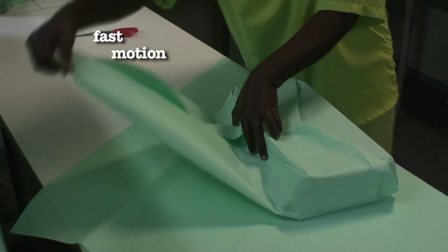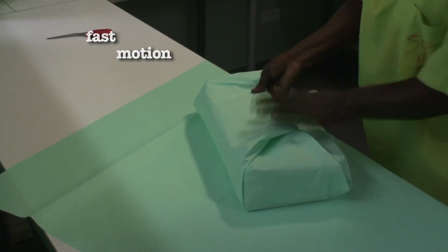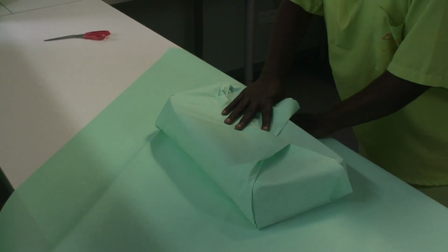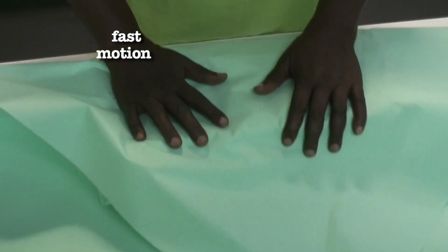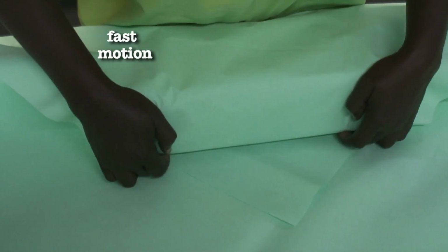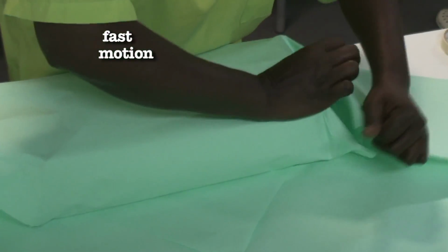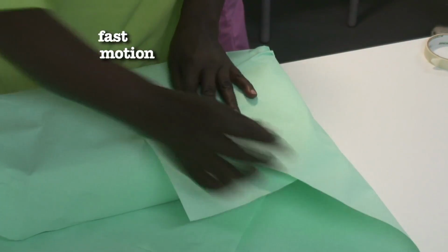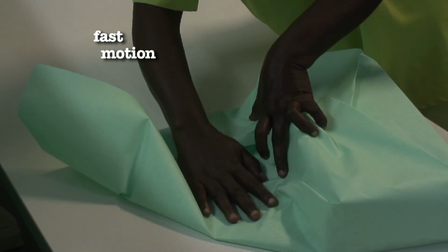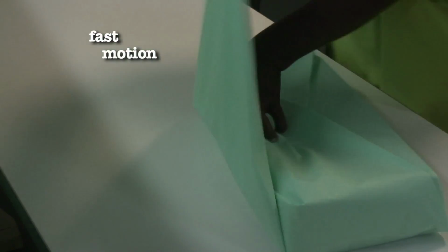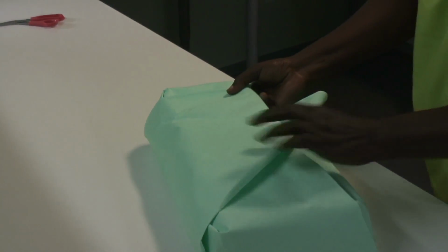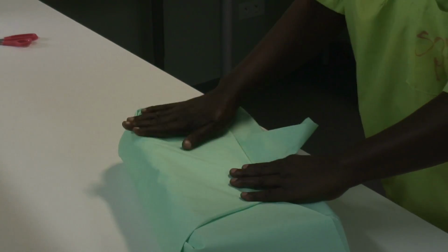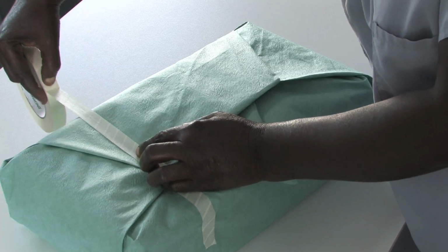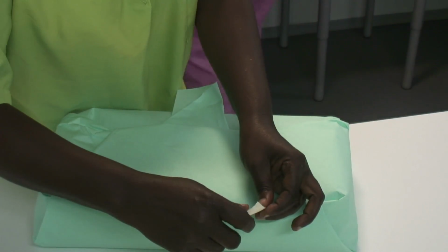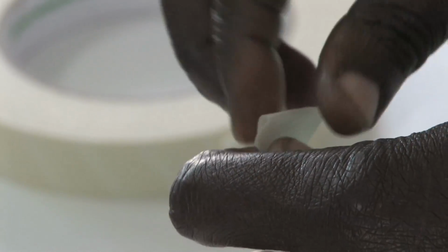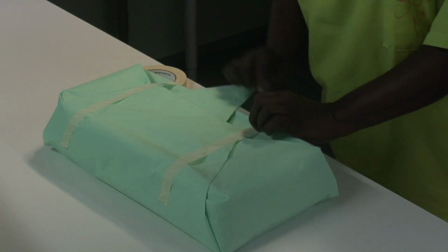4. And finish by covering everything with the last corner, which is folded over the pack and tucked in. 5. Repeat this operation with the second sheet. Seal the pack with the autoclave indicator tape. Fold the end of the tape back on itself to make it easier to open the pack. A pack that is difficult to open can cause a loss of sterility.